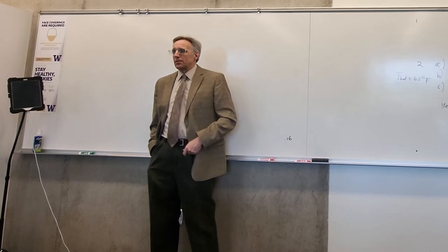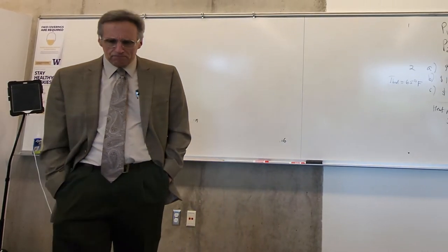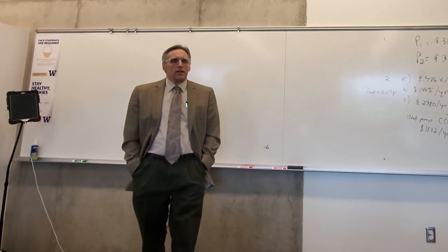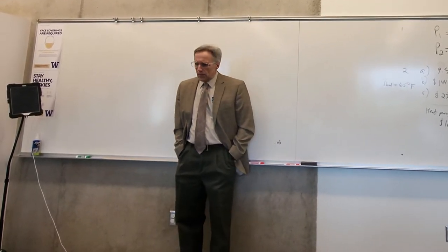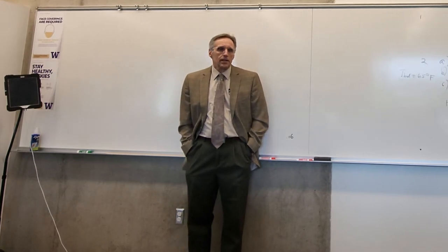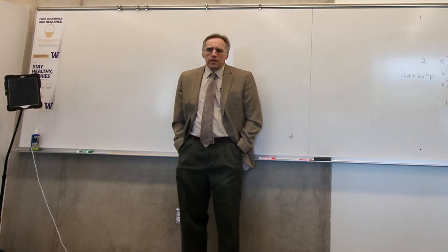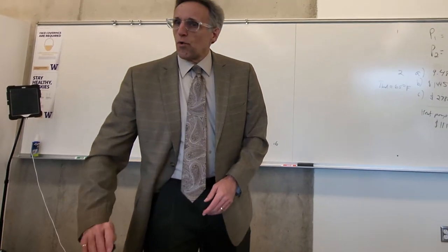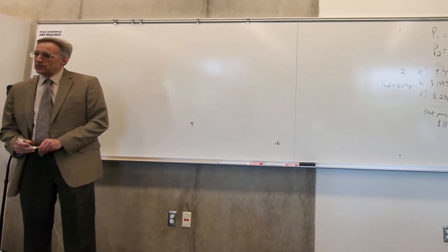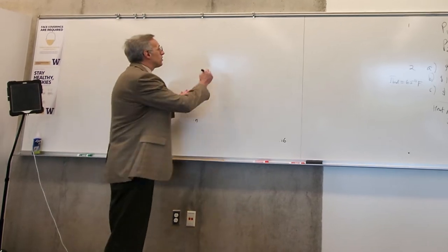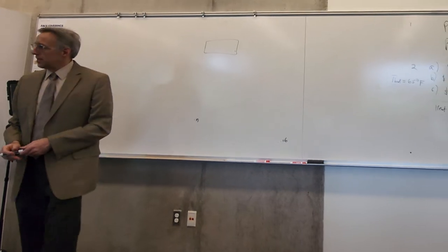Water source heat pumps are starting to grow. I'd be interested to hear. I would not advise a client, based on what I did over the weekend, to heat water up to 140. I think 120. Now, the systems that I'm familiar with, and these are becoming more popular, are air source heat pumps. And what do you do in this situation? Now, in a household, you're only going to heat water to 130. 130 degrees is your hot water temperature.